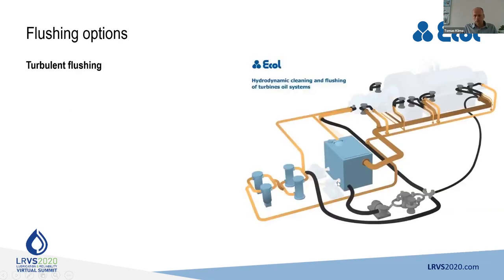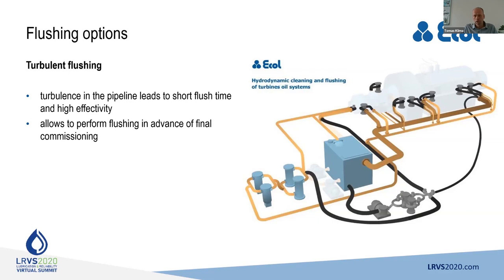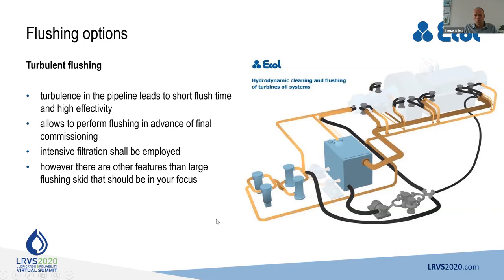The turbulent flushing is where we want to reach the turbulence in pipes that leads to short flush time and high effectivity using a special flushing skid, which is also allowing us to perform the flushing in advance of commissioning. Intensive filtration shall be employed. However, there are other features than the flushing skid that should be in your focus.